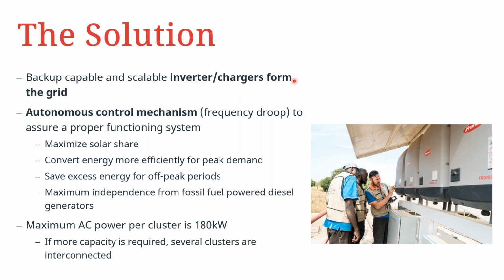We would also have to ensure that there is an autonomous control mechanism. And in this case, for a Fronius grid-tied AC coupled system, we are talking about a frequency droop principle that assures the proper functionality of this system overall. In addition to that, this would allow you to maximize your solar share by converting energy more efficiently during peak demand periods. For an AC coupled system, we would like to see the peak consumption being during the day, when the PV inverters, or the Fronius inverters in this case, are able to convert energy very efficiently.